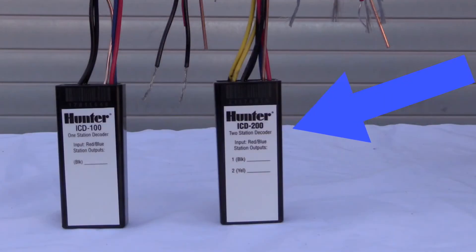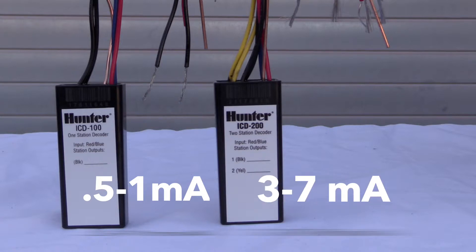Note that the mA draw for multi-station and special device decoders will be higher. Generally, decoders for single valve operation will draw 0.5 to 1 mA. Multi-station, pump, or sensor decoders will draw 3 to 7 mA. The as-built drawing can help you identify if these are used in your system.